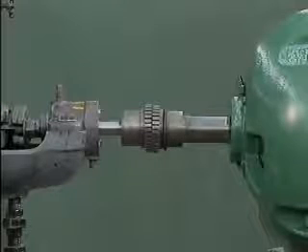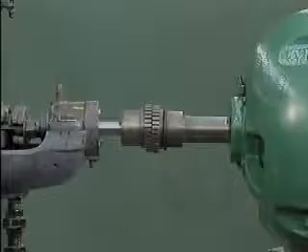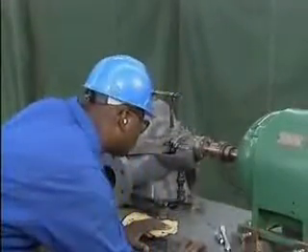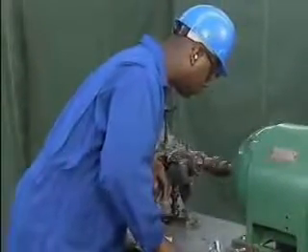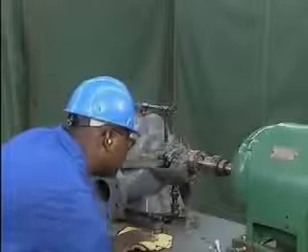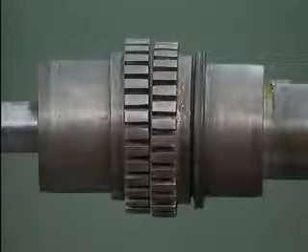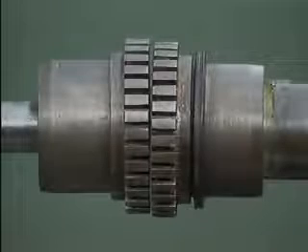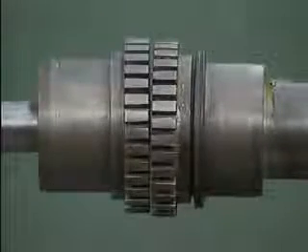The motor has already been positioned so that the space between the coupling hubs is within the manufacturer's recommended range. The mechanic begins the procedure by visually inspecting the coupling hubs to determine, as best as possible, what needs to be done to align the two shafts. From the side view, it looks like the hub of the motor is slightly lower than the hub of the pump, and that the motor is angled downward. In other words, it looks like there's parallel and angular misalignment in the vertical plane.